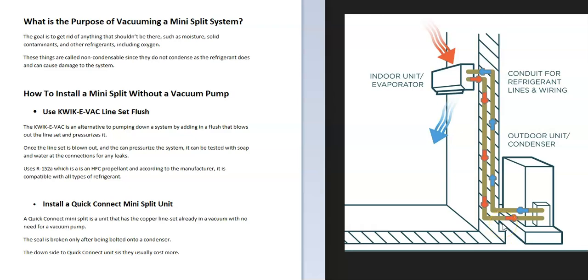All of this needs to be removed so the system lasts a long time. When you put a vacuum on it, that pulls it all out. The most ideal way to install a mini split is to use a vacuum pump, which is the recommended method for most mini split manufacturers.